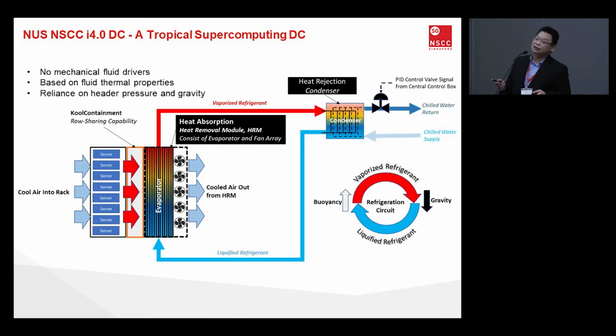So a bit on the design. As I mentioned, all the servers take cold air into the rack, take away the heat, and it comes out through the rear door as cold air. The gas goes in from the bottom, gets heated up, gets vaporized, and goes back to the condenser. After that, it gets cooled down by the chill water from the building and comes back in as a liquid.